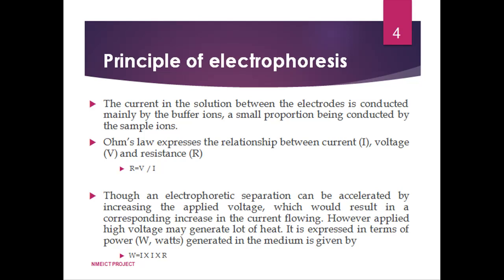Though electrophoretic separation can be accelerated by increasing applied voltage, which results in a corresponding increase in flowing current, the applied high voltage may generate a lot of heat. This is expressed in terms of power — watts generated in the medium — as given by the equation shown in the figure. Most of the power generated is dissipated as heat.